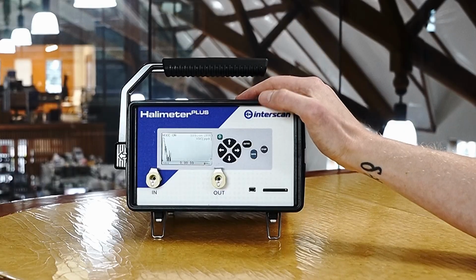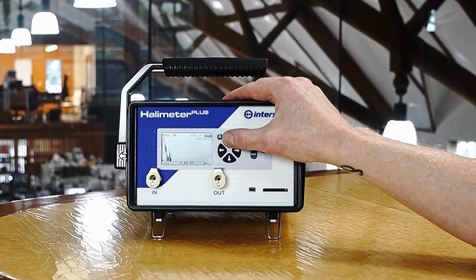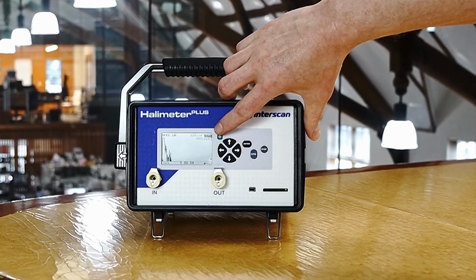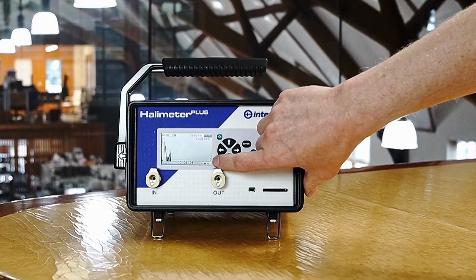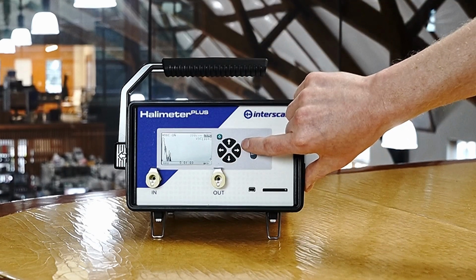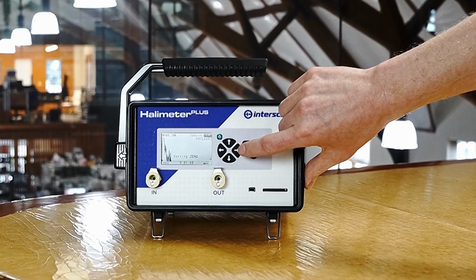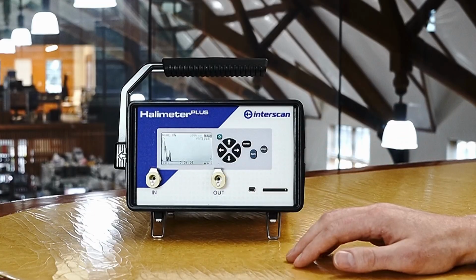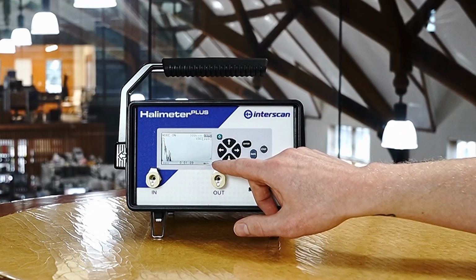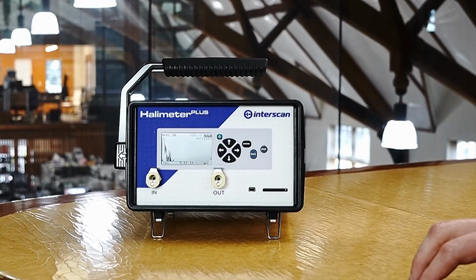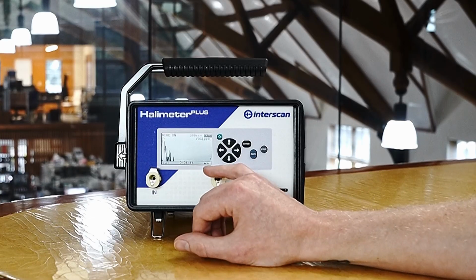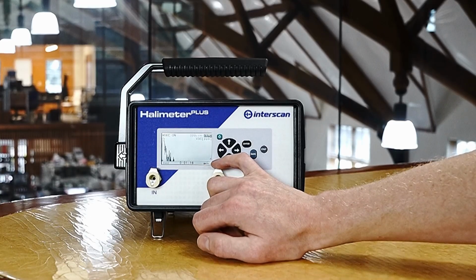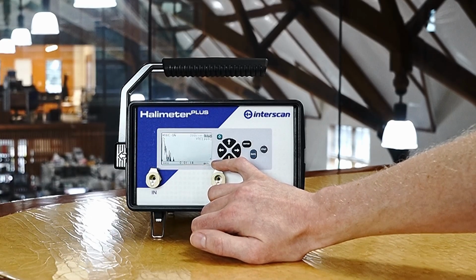From here, I'll show you how to zero the device. You will just navigate up. The 0 is highlighted at the top. We have a 0 down here, which is good. We'll press enter and that will reset your 0. And you should see some fluctuations here.